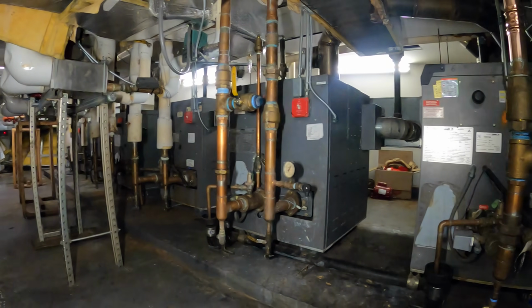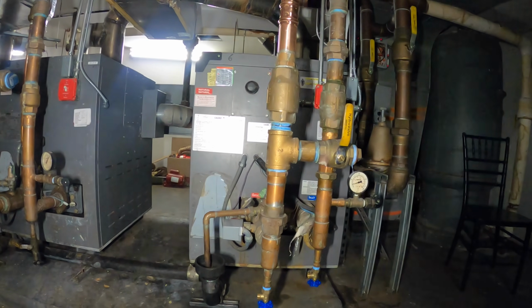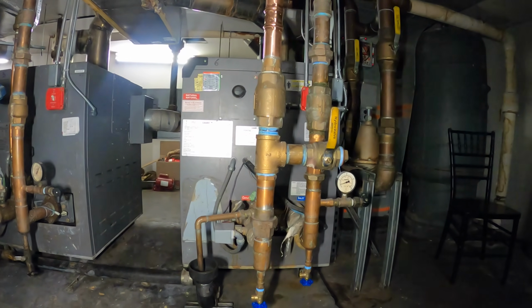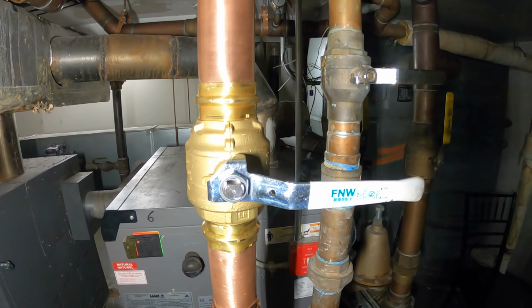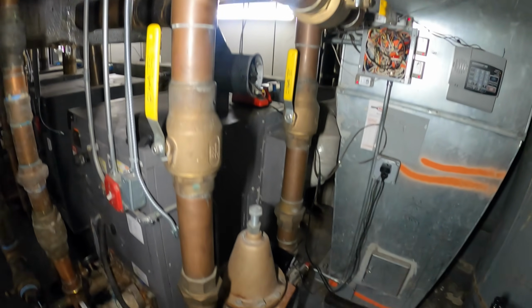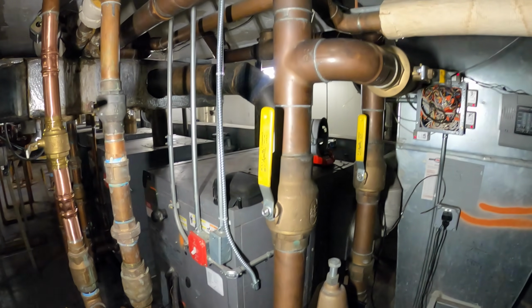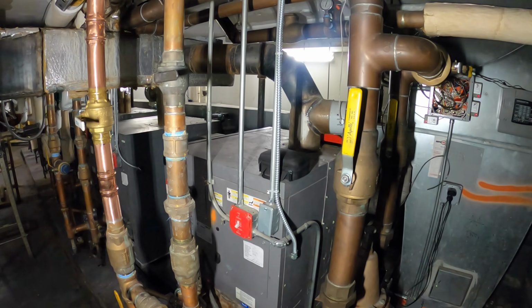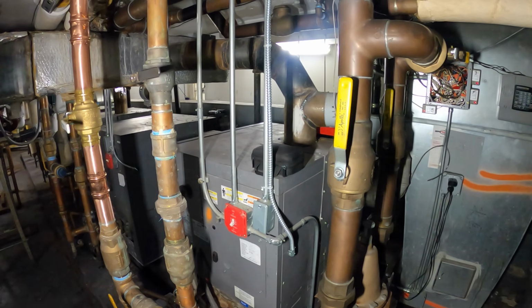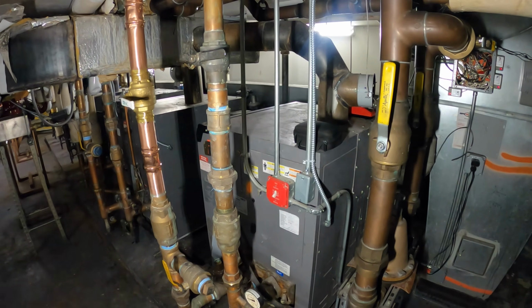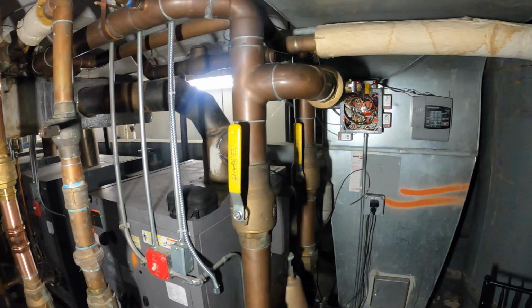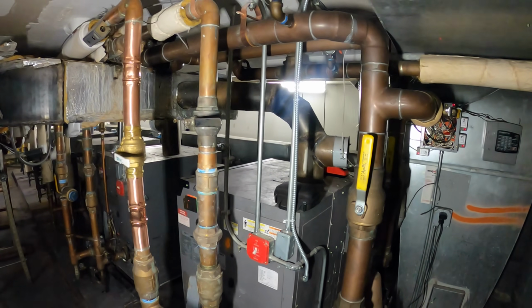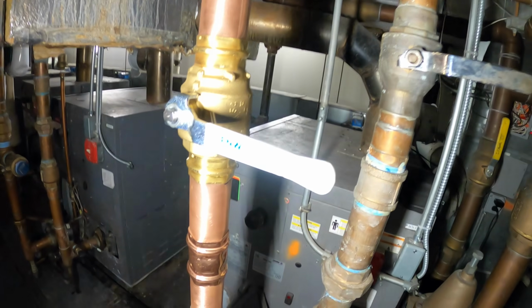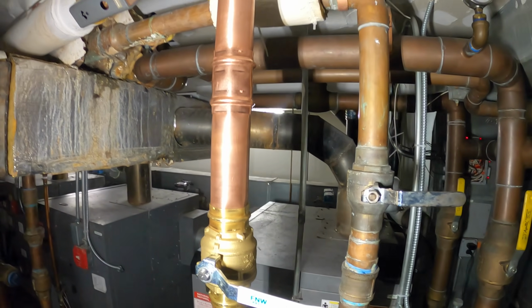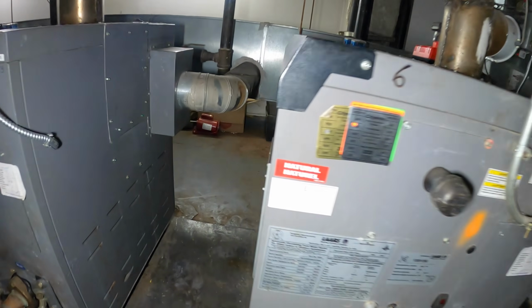Thank you to everyone tuning into Jumperman Tech. We have this boiler here, boiler number 6, and it has a faulty pump. What was happening was there was a valve here that didn't hold, so we had to shut down the main water supply to every boiler. When we were taking out the pump, the impeller was stuck in the pump header, and it was an absolute nightmare. We put it back, and when we opened it up, water was flooding everywhere through the pump. It was destroyed at that point. We couldn't stop the water, but luckily I had this valve and shut it down. Now we're back. They want us to change the pump, and we have to change the pump header. Let's come back here, tight spot.